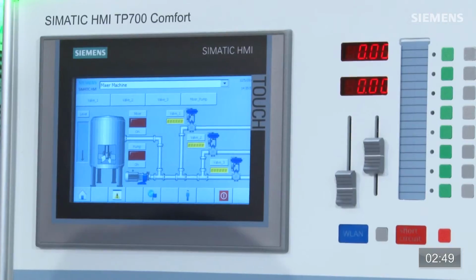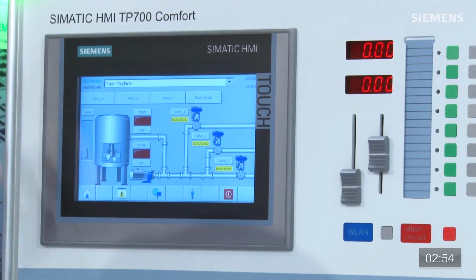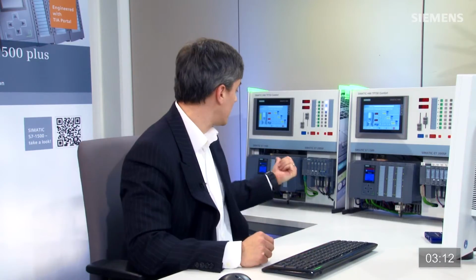However, in our new system, as it starts to power up, you'll see immediately that we actually have hash marks across the valves, so they're not receiving any communication. The level doesn't work either. And here in a few seconds, it's going to go into a stop mode, and it has. I can actually take it back to stop and back to run, and you'll notice that it doesn't work. That's because the actual code that would make this function doesn't reside there. It only resides on the original card, not on this copy card. Okay, so I've got my copy protection.